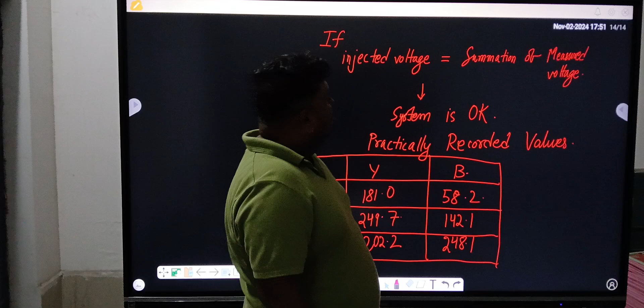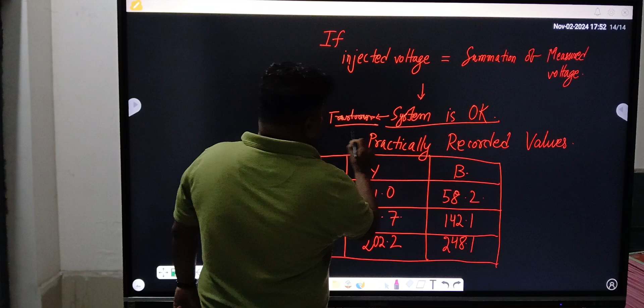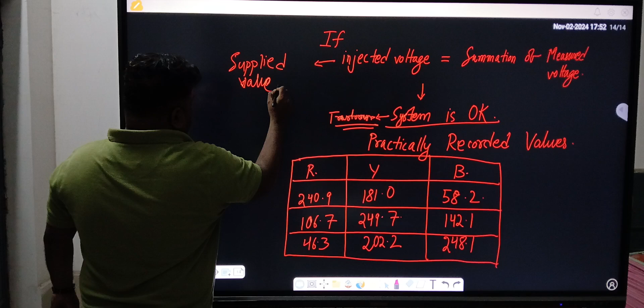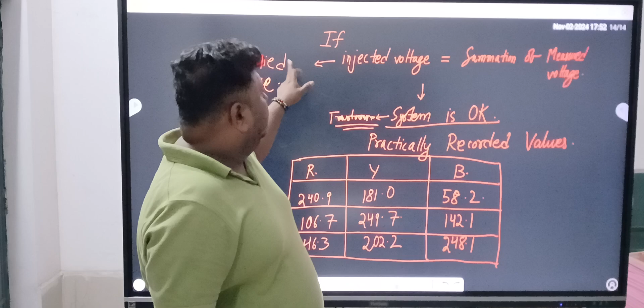Then how can we conclude that the system is okay? System here means the transformer, and the system components are the transformer windings and the limbs of the transformer. So how can we conclude that the system is okay? If the injected value, meaning the supplied value, say I have given a single phase supply of 220 volt to any of the phases and repeated the procedure, that value is known as the injected value and should be equal to the summation of the measured values.